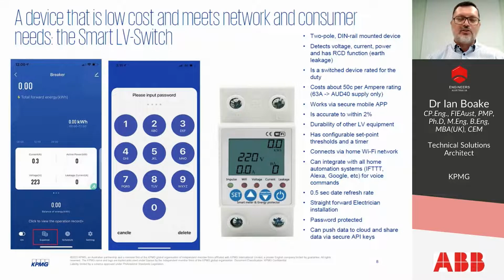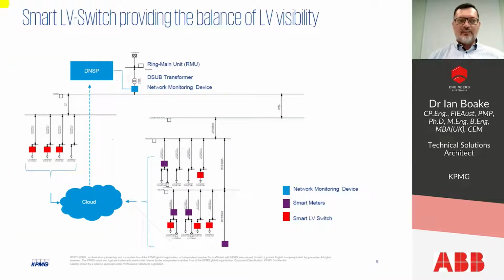So what does that actually look like in terms of a network? In bringing this all together, I present to you a single line diagram. At the top of it, it shows the ring main unit, which is the interface device with the medium voltage network, as well as the distribution sub-transformer, and then the aforementioned network monitoring device, which provides a very coarse view of voltage and flows within the network. The DNSP have that network monitoring device, the blue device, under their control, and they monitor that. What the consumer installs are the smart meters, those specifically that get DER at their premises, and that's represented by the little inverter blocks.